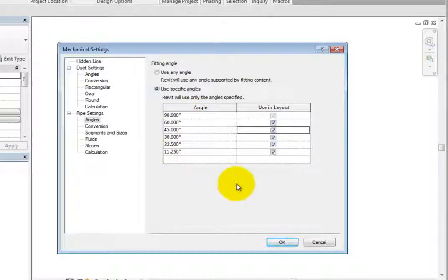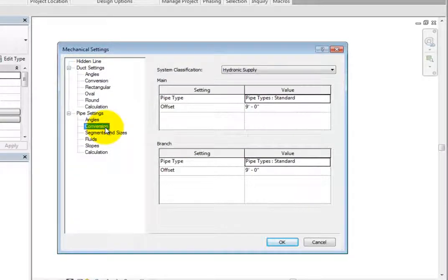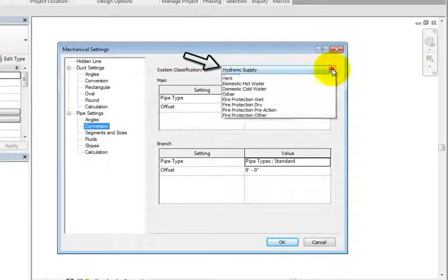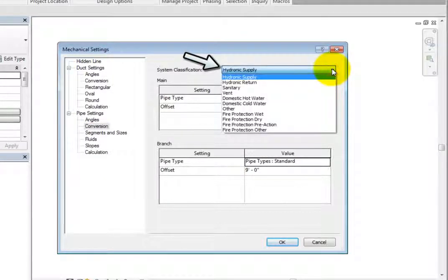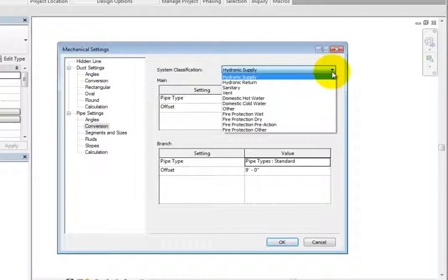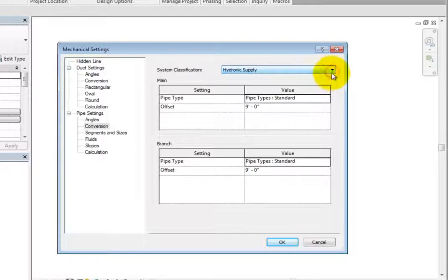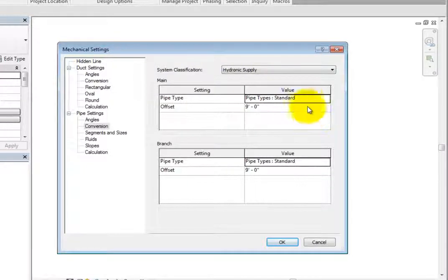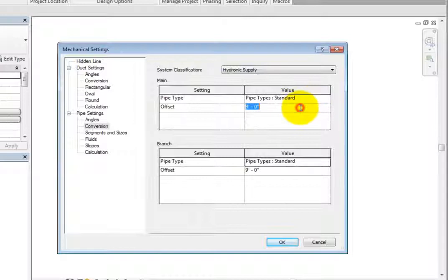When you select Conversion under pipe settings, the available options control how the pipe systems will be routed using the routing solutions. You can control the system classification using the dropdown at the top. Here, you can select numerous piping system types, such as hydronic, domestic, and fire protection systems. The main and branch settings then control how those pipe systems will be routed using the routing solutions. The main settings allow you to control the pipe type and offset for main pipe runs for each of the system classifications.